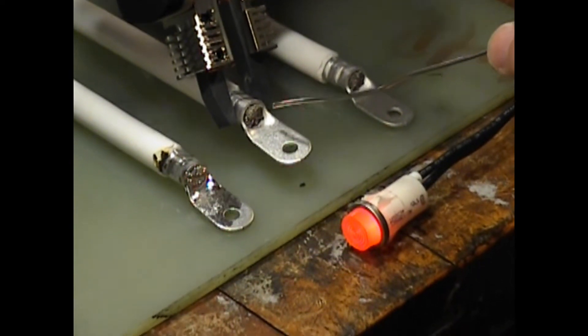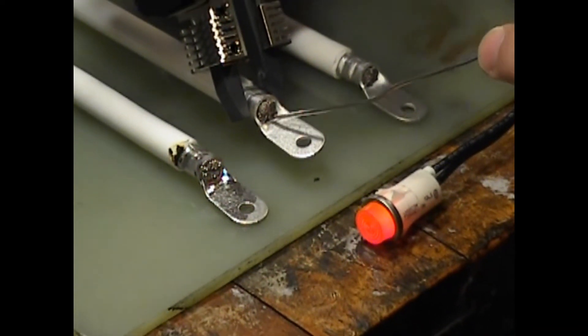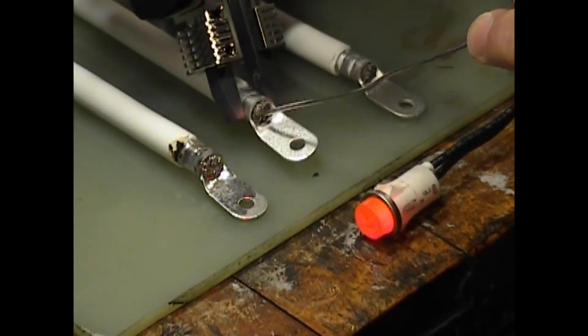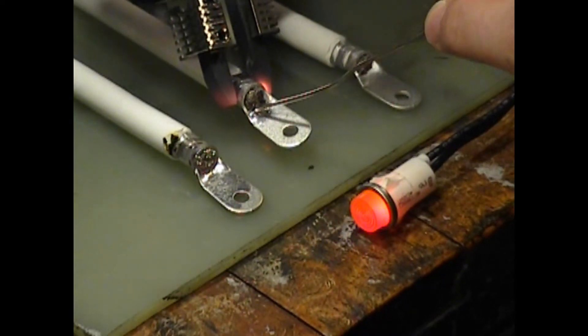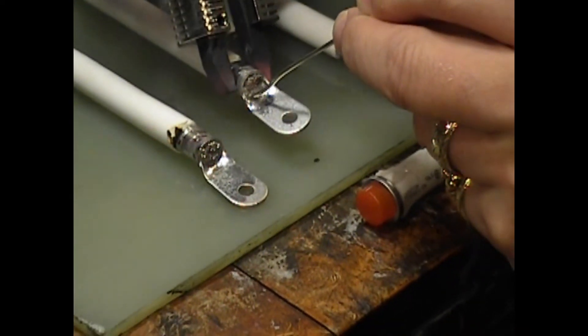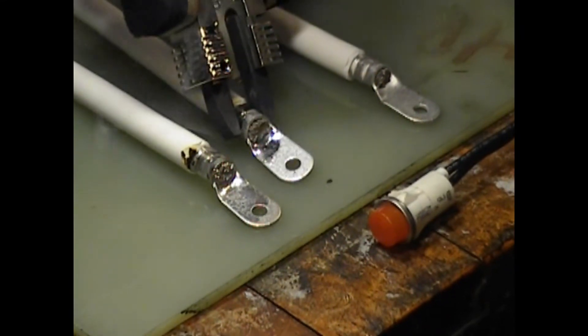The purpose for soldering crimped on terminals is to improve the mechanical connection and the electrical continuity along with creating a hermetic seal to protect the connection against oxidation or contamination caused by humidity or other environmental hazards.